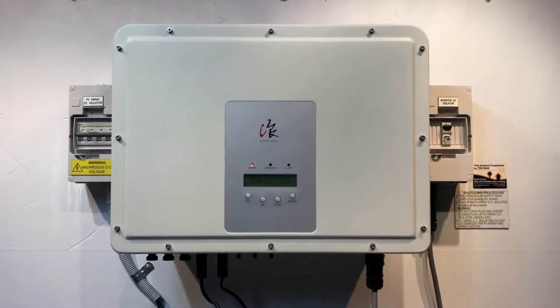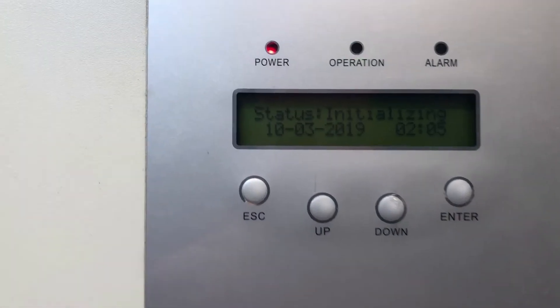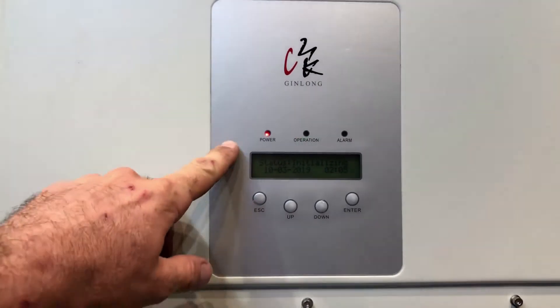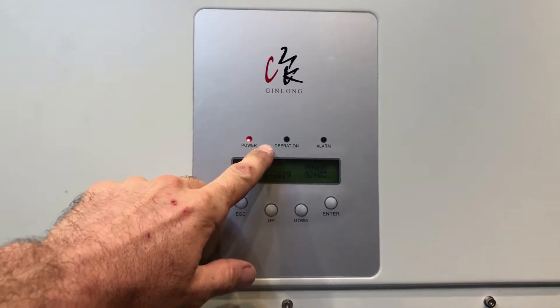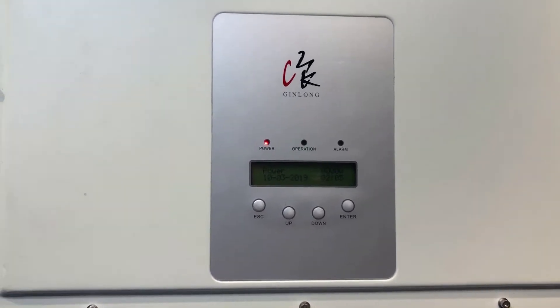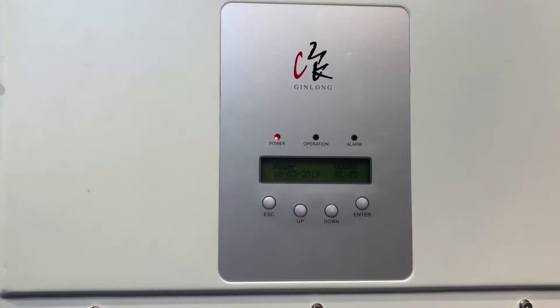Today we have a Ginlong inverter and if we have a look at the screen of this one, it's just showing status initializing. You can see the power light is on full and constant, and the operation light is flashing. If your inverter is having the operation light flashing like that, it actually means this inverter is not working.